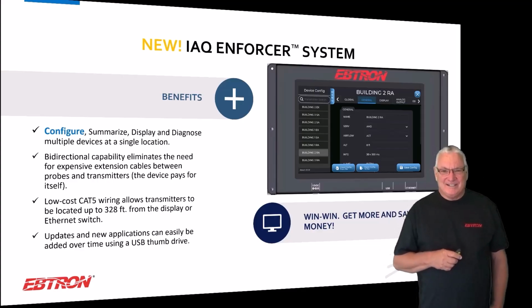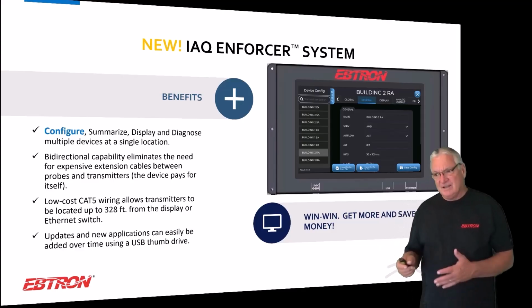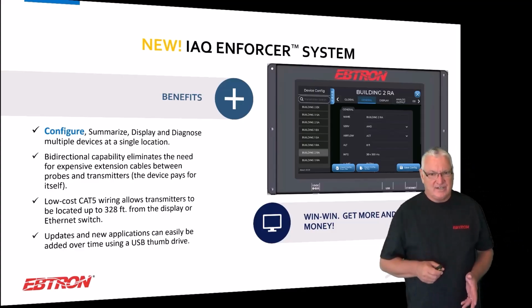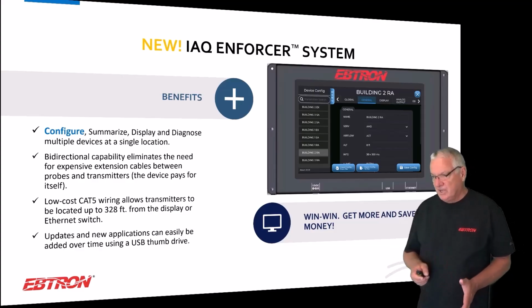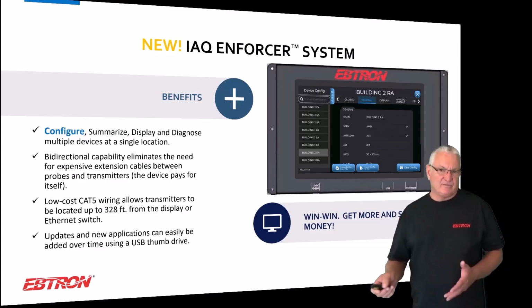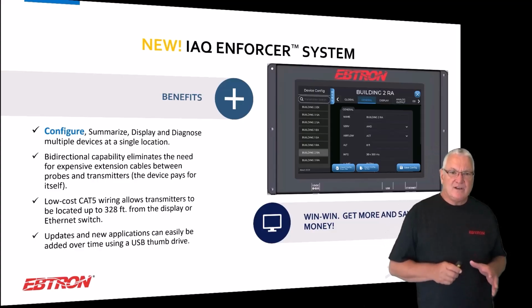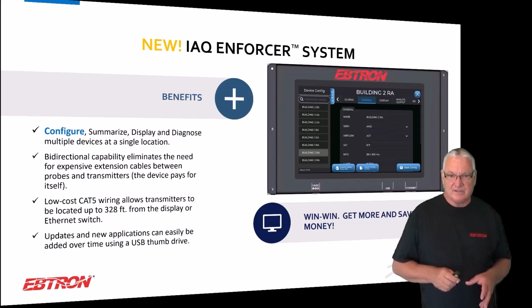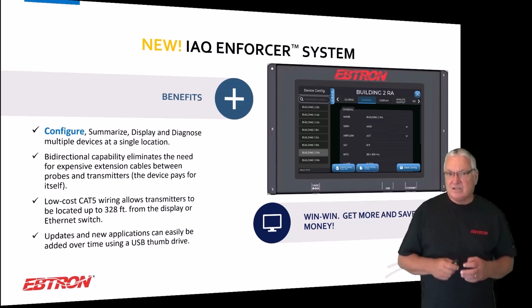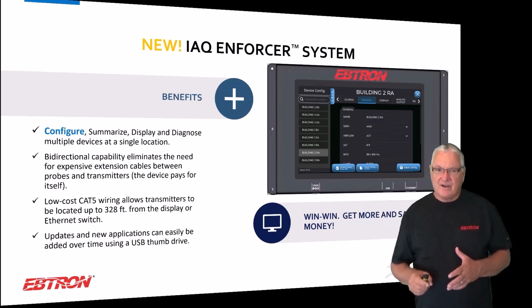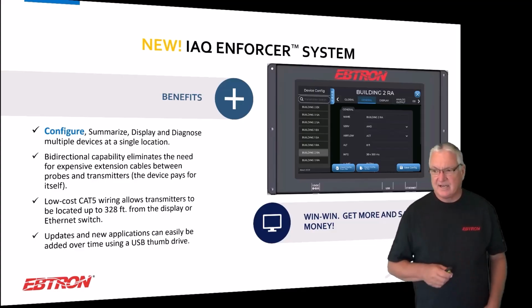Slick applications here. One of them is configure, okay? So one of the beauties of this device is you locate, let's just think about a mechanical room as an illustration. So you have all these different flow meters in the mechanical room. Supply, return, outside air, maybe you have 2 or 3 air handlers, okay? This device will support up to 16 individual devices or transmitters, okay? So you have this in a mechanical room, and you want to be able to do everything from this one point, okay? And one of the things you have to be able to do is be able to configure it if you want to modify or look at how this unit is set up.